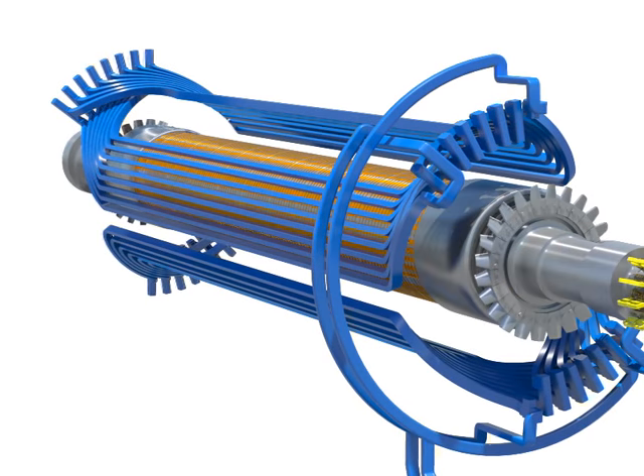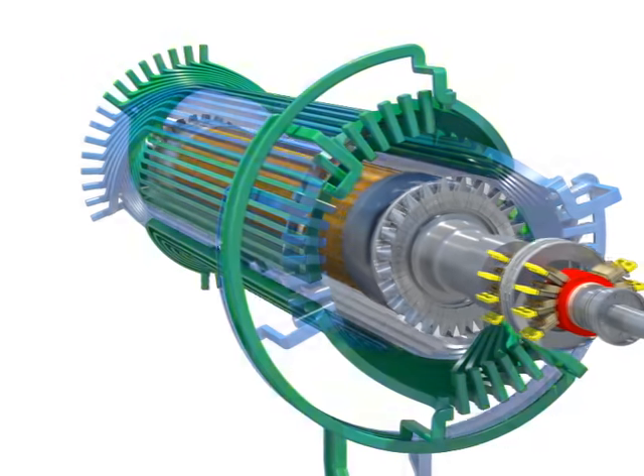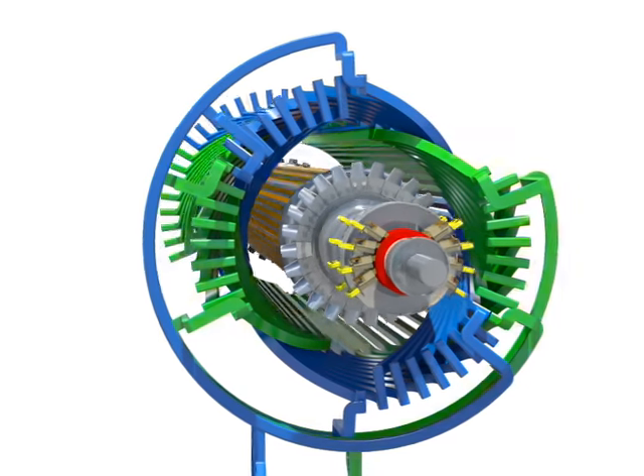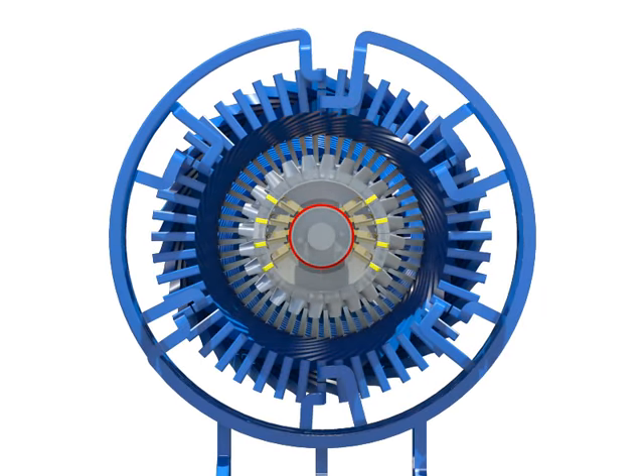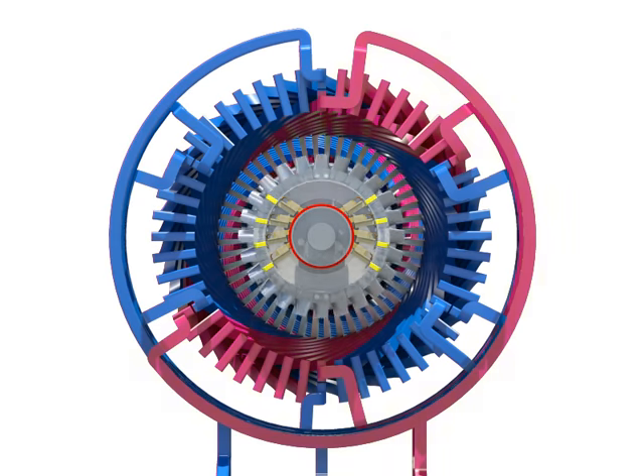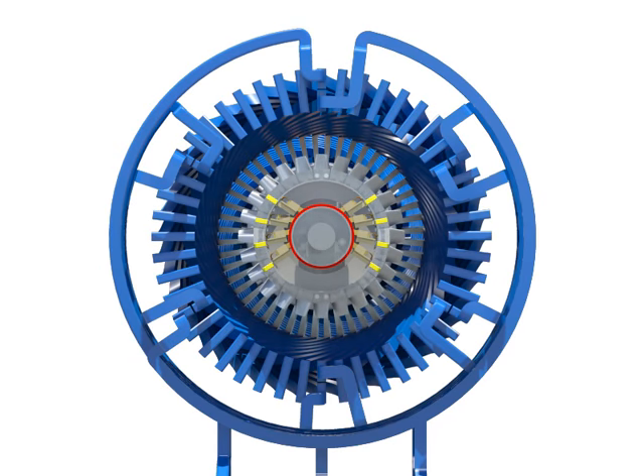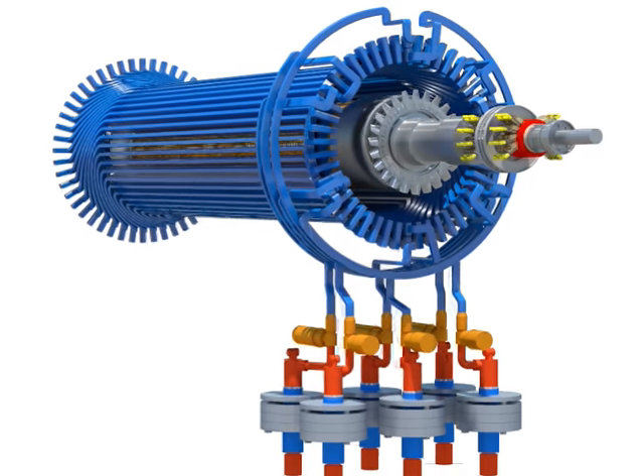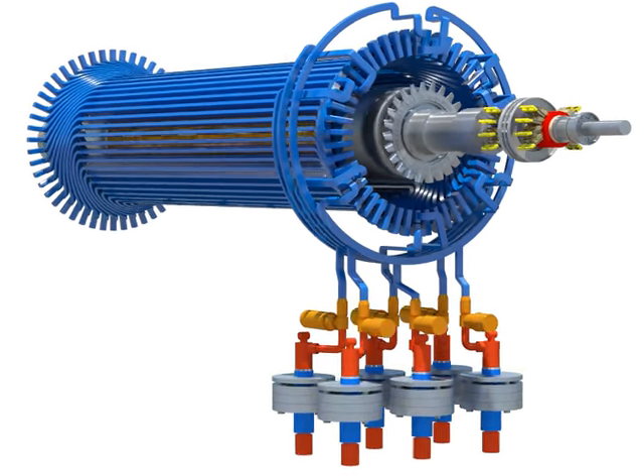The stator coil interlinking with the magnetic flux provided by the rotor forms electromotive force according to the electromagnetic induction law. By placing six winding groups at intervals of 30 degrees, six-phase alternating current which has 30 degrees of electric phase angle is formed.